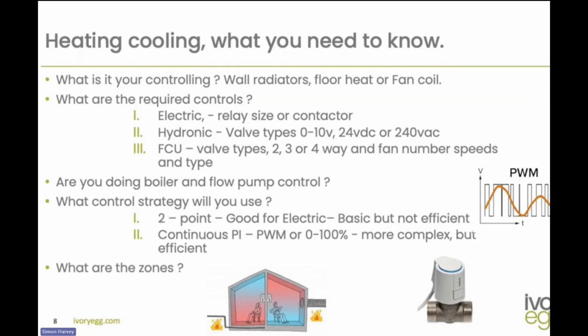Then we've got continuous PI or PID, which is proportional integral. And PI is a constant calculation from the last output to the newest input. Basically what happens with PI, the closer it gets, the more calculations it does, and it starts backing off the continuous control of the valve or the load. Okay, so you can imagine you've got a set point and you've got a target, or you've got a room temperature. As for PWM, you've got two types of continuous, I should say again.